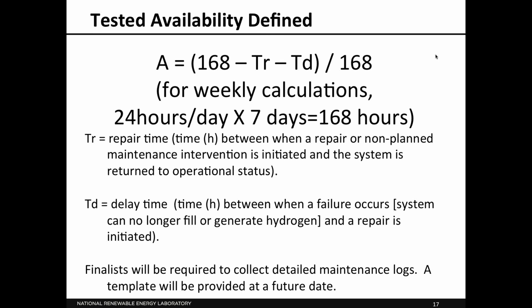Delay time is logistical delay. It's between when a failure happens, or the system is no longer filling or generating hydrogen, and a repair is initiated. And this may be reporting, time to learn about the failure, time to get parts, time to get people on site. All of those logistical delay kinds of things will count against availability as well. And that's all that goes into the numerator. The denominator then is just the total number of hours in the week.